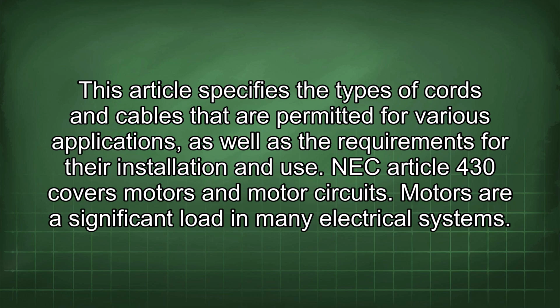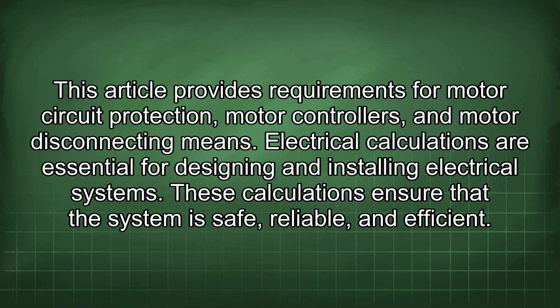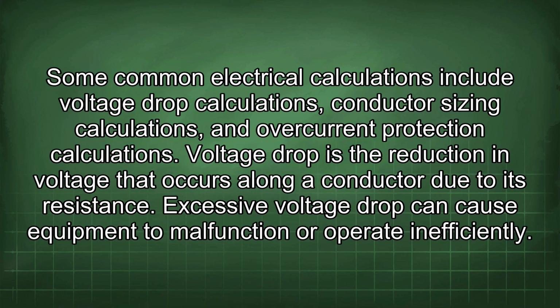NEC Article 430 covers motors and motor circuits. Motors are a significant load in many electrical systems. This article provides requirements for motor circuit protection, motor controllers, and motor disconnecting means. Electrical calculations are essential for designing and installing electrical systems. These calculations ensure that the system is safe, reliable, and efficient. Some common electrical calculations include voltage drop calculations, conductor sizing calculations, and overcurrent protection calculations.